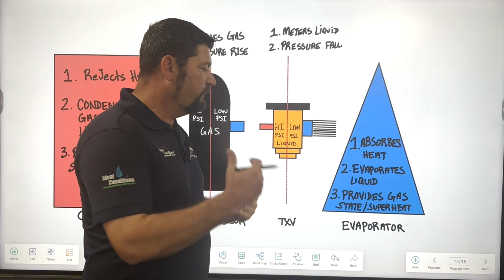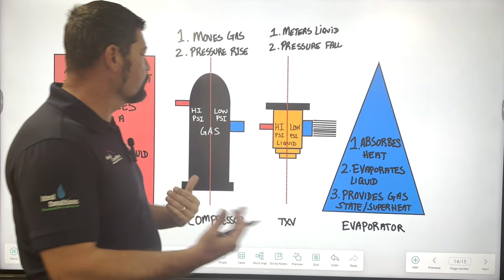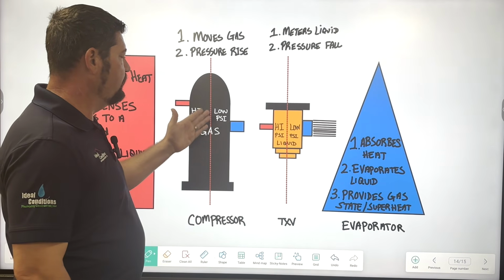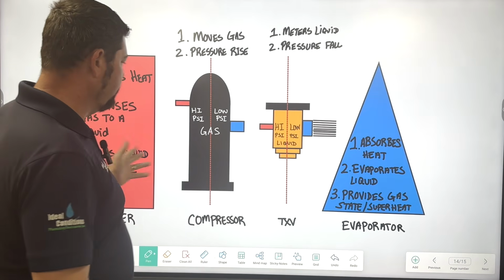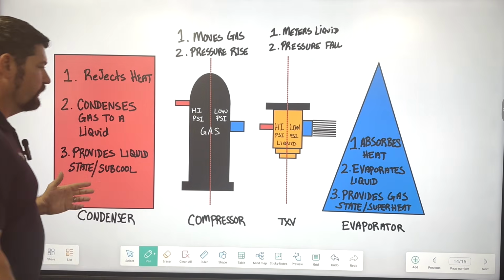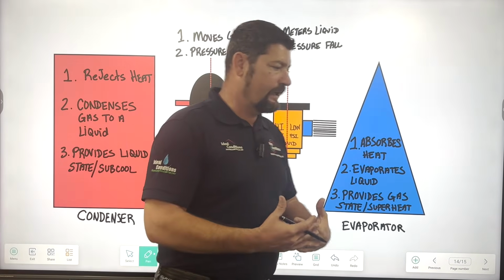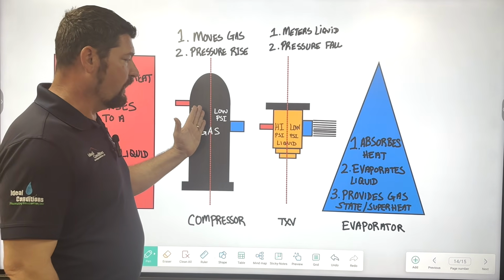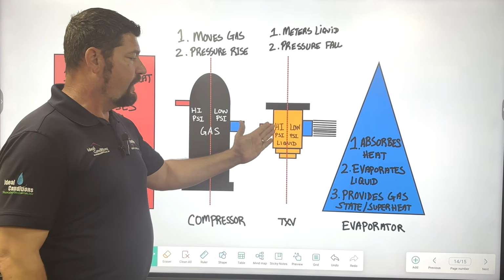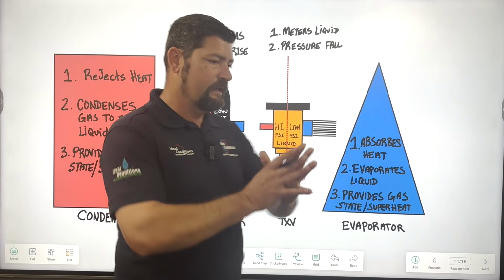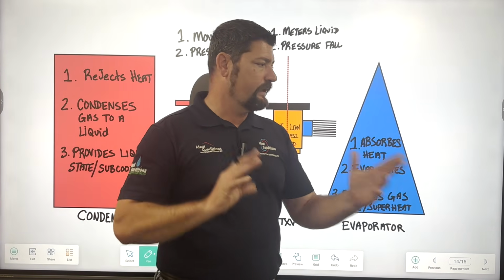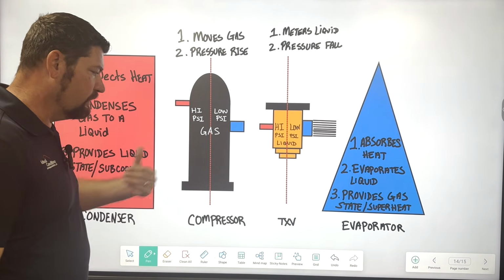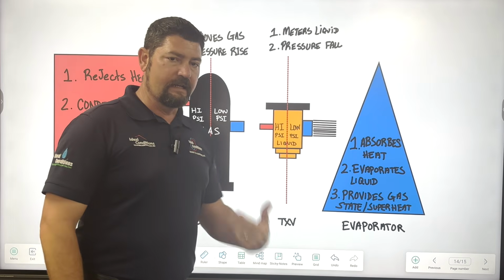And so when we see these values, when we see numbers moving around, I can't take a high PSI and a low PSI and then look at my superheat over here, my subcool over here, and say that I have a bad critical component when my pumping ratio is solid and the values are not moving in the right direction. We have a superheat subcool video that I want you to check out if you haven't done so already that clearly expresses that using a cup analogy.